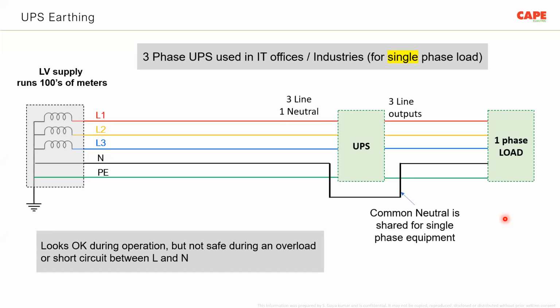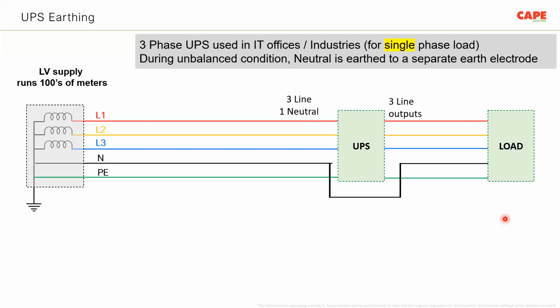Now, anyway, this kind of circuit cannot operate, or probably it may operate if there is no neutral current. That means if the load is completely balanced, then this kind of system may work. But whenever there is an unbalance in the system, or whenever there is a neutral current flow, what happens is the voltages of the system start dancing. It completely changes and it will start with harmonics, and a lot of issues are going to come.